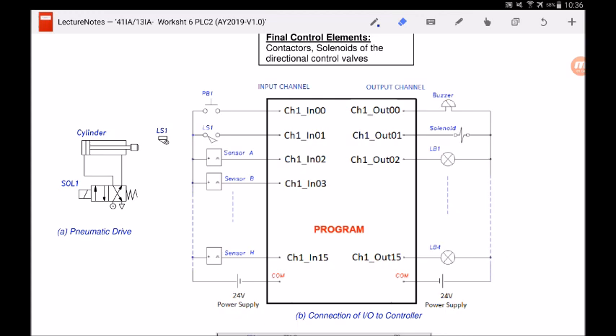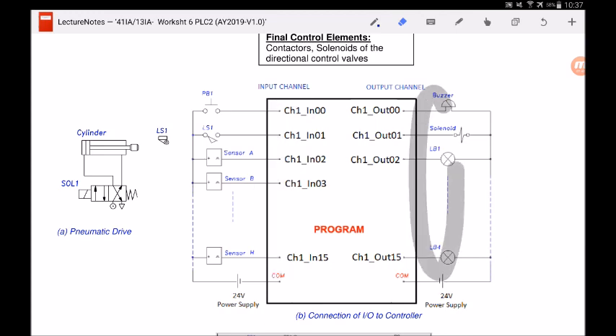Looking at the schematic diagram in figure 4b, we connect all input elements to the input card of the PLC, and all output elements and final control elements to the output card. For this particular PLC model, the input card has 16 channels, so you can connect up to 16 input devices. Similarly, you can connect up to 16 output elements and final control elements. You can expand the PLC's capability by adding more input and output cards, but in our lab we only have one of each, supporting up to 16 inputs and 16 outputs.